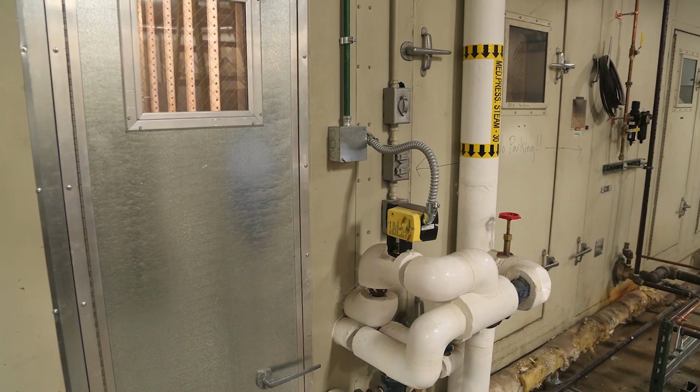If you're going through piping, then how much of that steam is collapsing back into condensate going from point A to point B as well. So both of those are important pieces. You know how much you want in there, but how much do you have to have at the start so you can achieve what your goal is? And there's different ways that you can mitigate some of that. Insulating piping, you want to keep it as steam. You put the energy into it, let's keep it as steam and not collapse it back into condensate. You can do the same thing within the airstream. Keep the tubes hot so they're not getting cool, causing that steam to collapse back into condensate. That's one way.